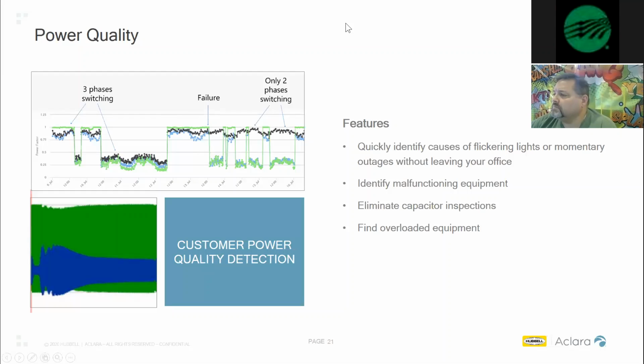So it was determined at the point where you see that Z phase stop switching, obviously, they were able to detect this using the sensors and the power factor data, that there was a blown fuse on that Z leg of that capacitor bank. Now, obviously, this isn't going to cause a severe power quality event per se. However, using this same power factor data, we're able to identify many times in the past a flickering light type power quality issue where lights are flickering and they can't quite figure out what it is. Using that power factor data, we were able to see some malfunctioning cap controllers that were causing short cycling of that cap bank itself. So it was using the same power factor measurements that you can identify these same type of anomalies or problems that were therefore causing actual customer interruptions. So it can tie into a performance or power quality type event.